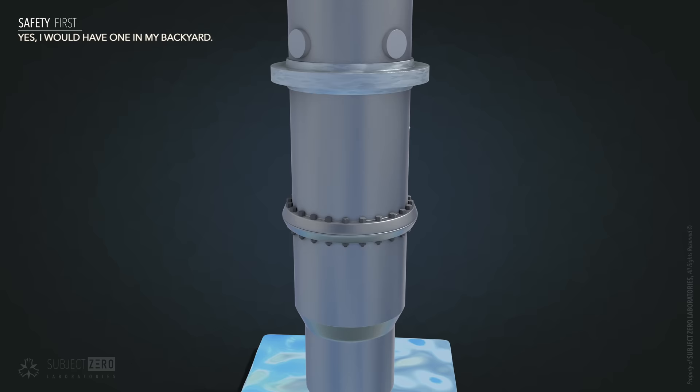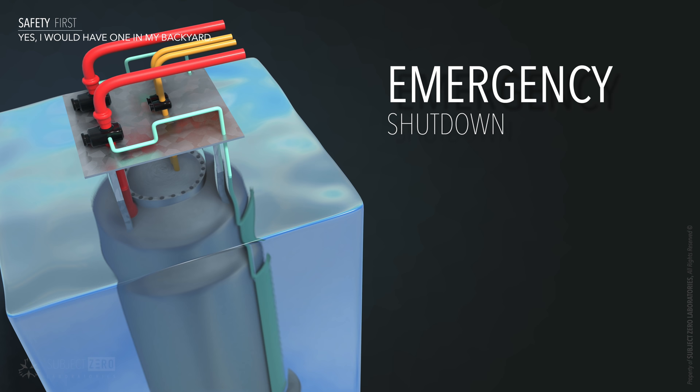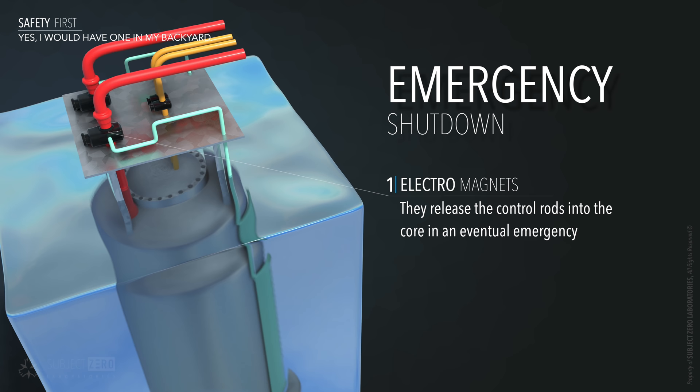Everything is self-contained, especially when it comes to safety. In an emergency, the SMR can shut itself down without any external help and remain cooled indefinitely. This is because the control rods are held up by electromagnets. In the event of complete power loss, the electromagnets stop working, releasing the control rods back into the core, blocking the reaction.